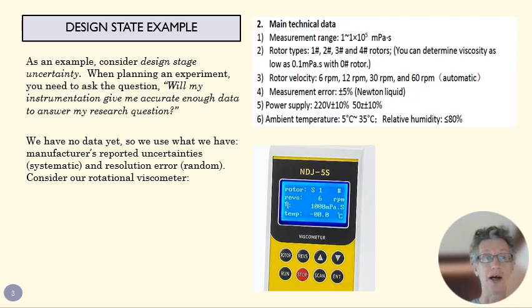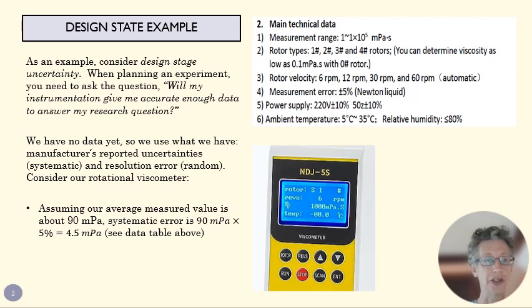So the way we do that is, for systematic error we would use manufacturer's reported uncertainties, and for random error we'll use resolution error. So consider our rotational viscometer, and here up in the upper right we have the manufacturer data from the manufacturer. In this case we would look up here and we'd say, okay, measurement error is plus or minus 5%. My average reading value is going to be at about 90 millipascals, so we do a little research to figure out where we thought most of our values would be. And I could see that my design stage systematic error is 4.5 millipascals.